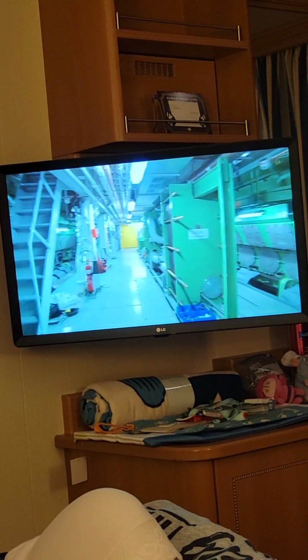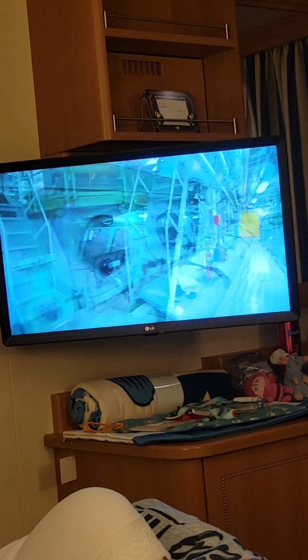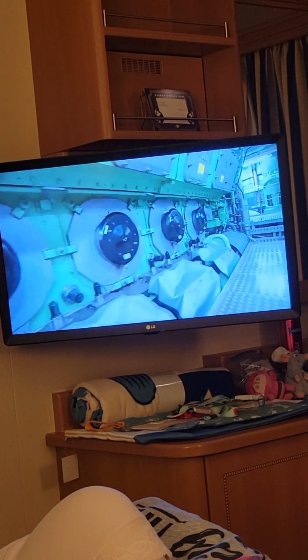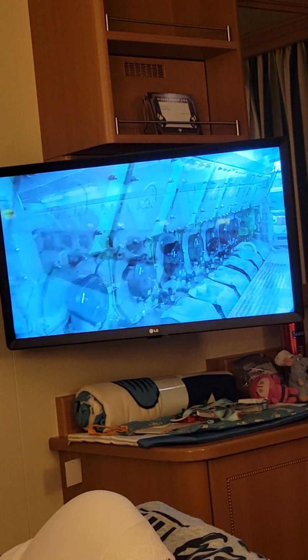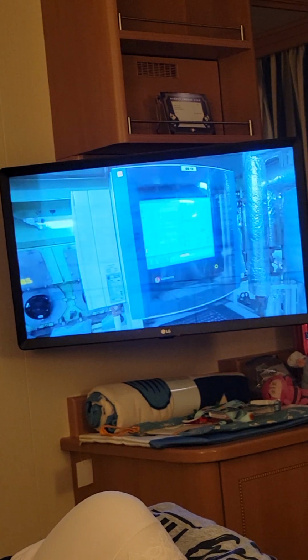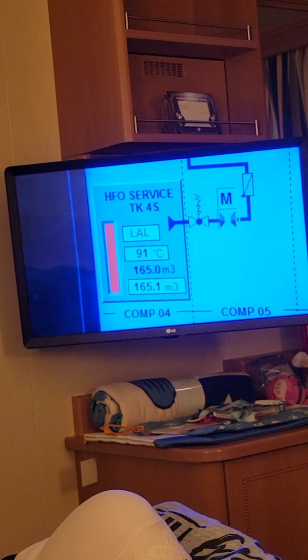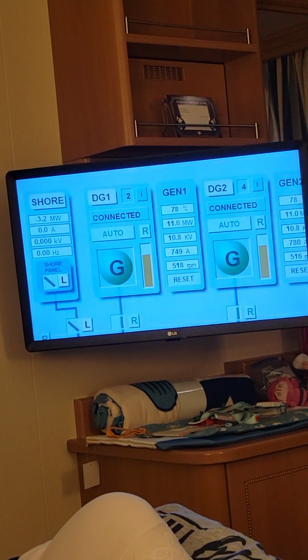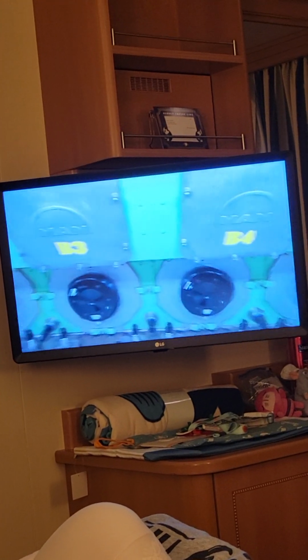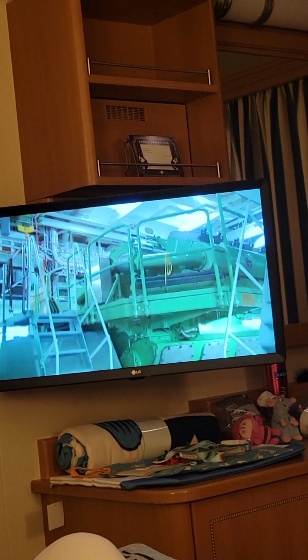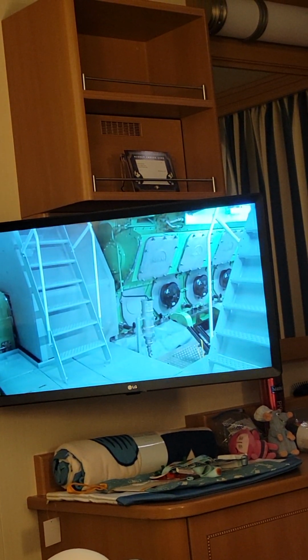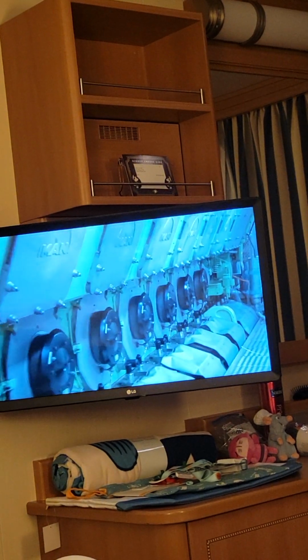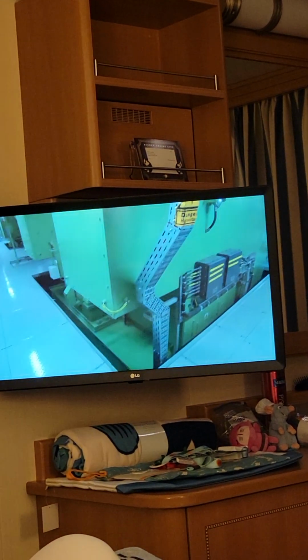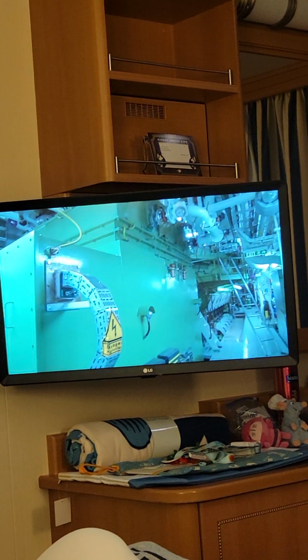The ship is equipped with 5 diesel generators: 3 V12s configured in the forward engine room, capable of producing 14.4 megawatts of power, equivalent to 19,000 horsepower per engine. And 2 V14s in the aft engine room, capable of producing 16.8 megawatts of power, equivalent to 22,000 horsepower per engine. That's over 100,000 horsepower powering the ship.